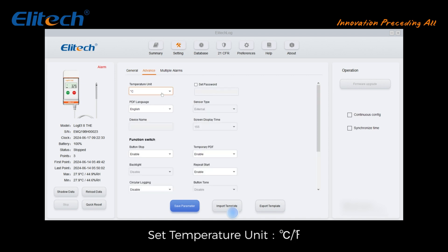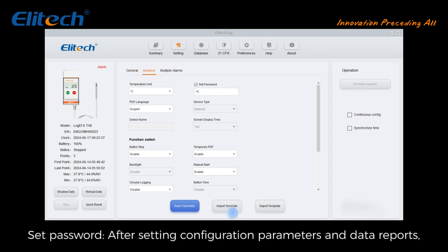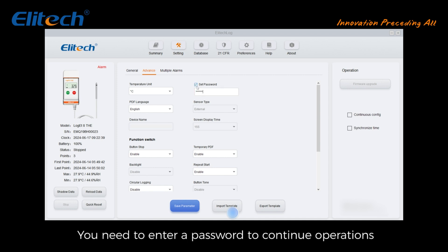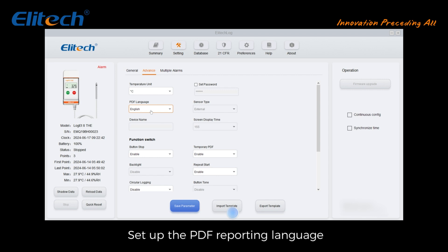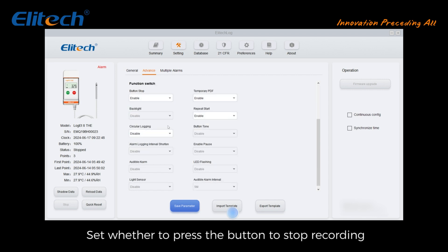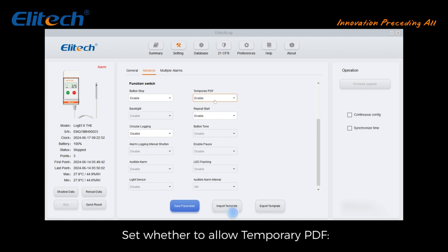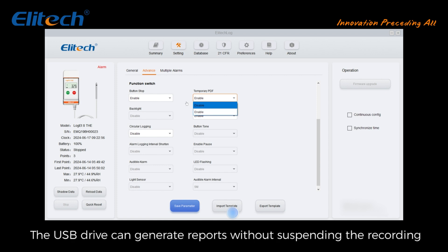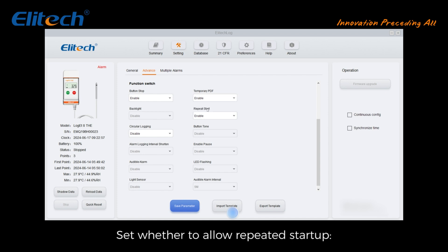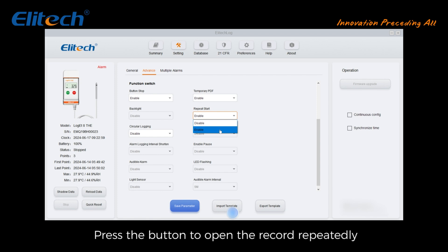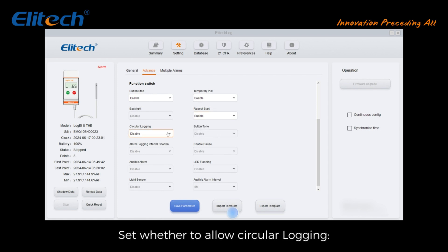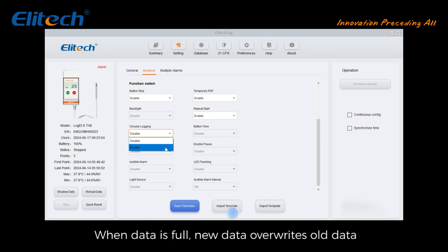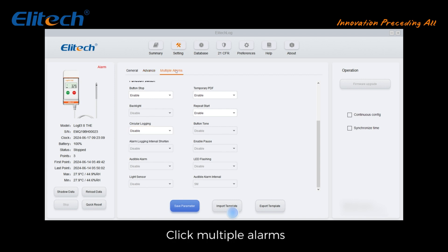Click Advanced to set the temperature unit (degrees Celsius or degrees Fahrenheit). Set a password — after setting configuration parameters and data reports, you will need to enter a password to continue operations. Set the PDF reporting language. Set whether pressing the button stops recording. When the device is plugged into the computer during recording, the USB drive can generate reports without suspending the recording. Set whether to allow repeated startup to open the record repeatedly.